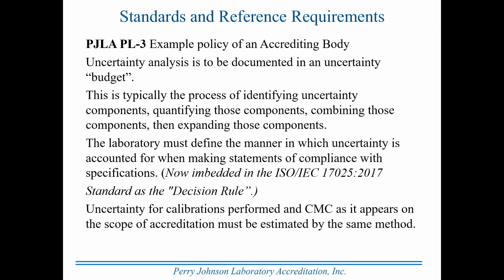Uncertainty for calibrations performed and CMC as it appears on the scope of accreditation must be estimated by the same method. That's a PJLA requirement, but it comes from an ILAC requirement, which was found in PL4. Bear in mind, ILAC rarely interacts directly with individual laboratories. They interact with accrediting bodies, imposing on the accrediting body a set of requirements. The accrediting body imposes those requirements uniformly, consistently on all the laboratories they accredit.